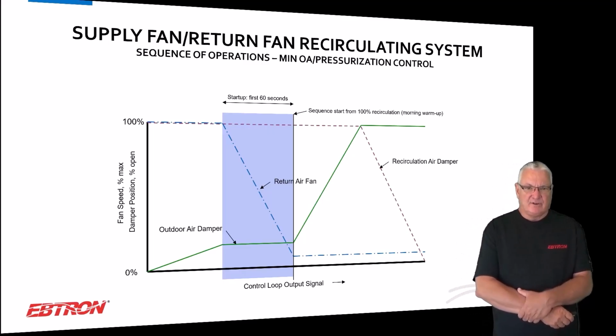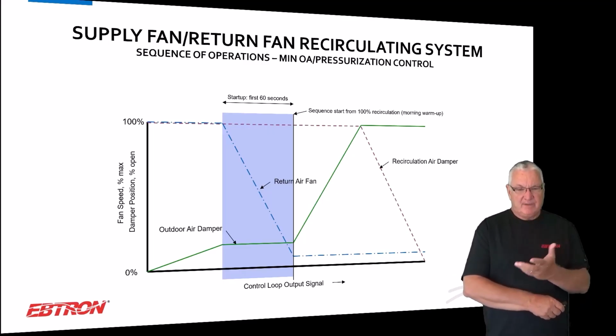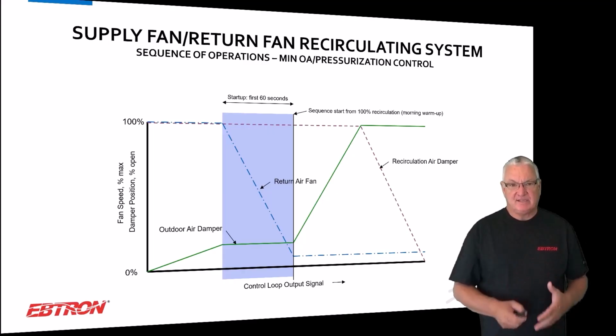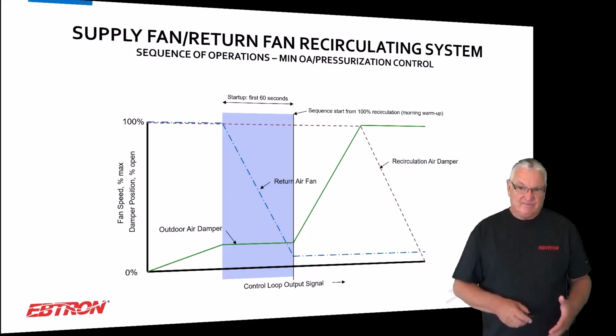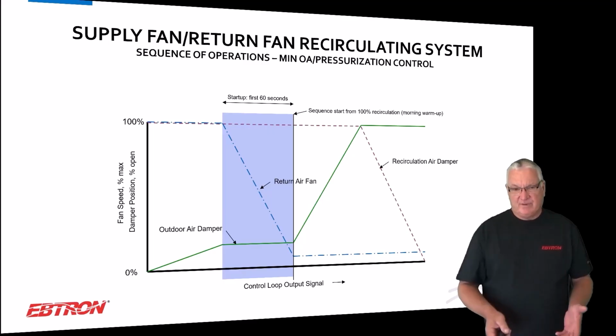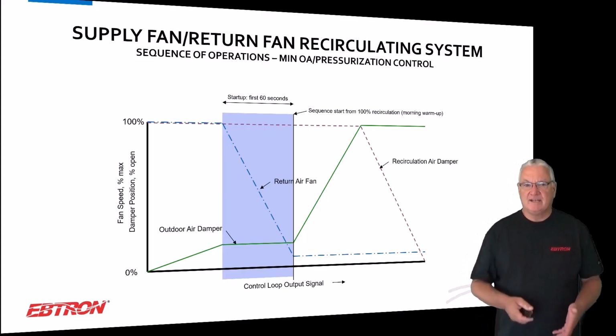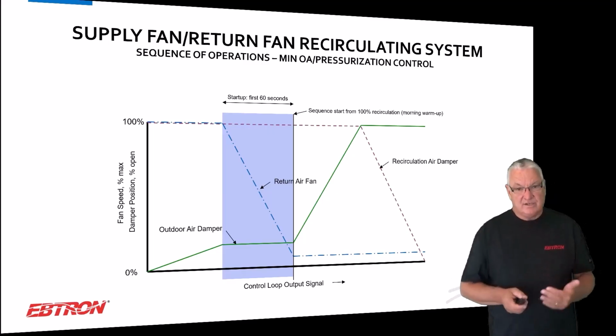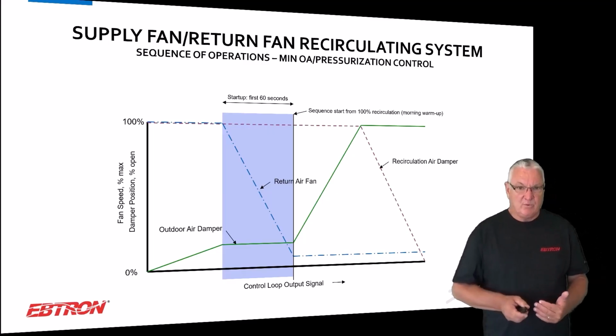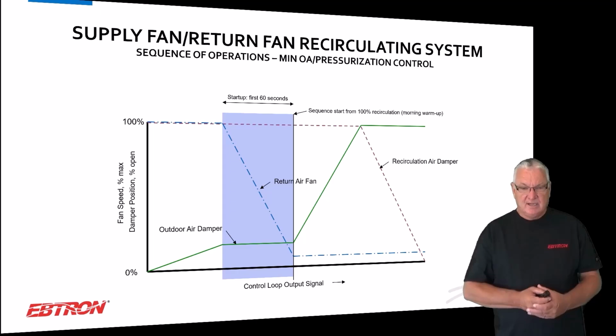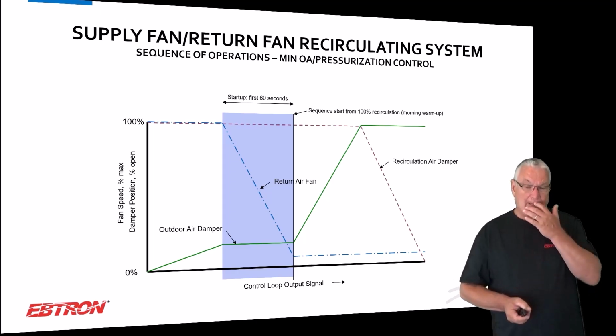There's a vertical line there that we put at minimum speed, and that's going to make the mixed air plenum as negative as we can. The supply side, depending on the system, could be driven by air changes, or because it's a VAV system. Whatever is driving it, it doesn't matter. It's going to do that. But we want to start with the return fan at its minimum speed.